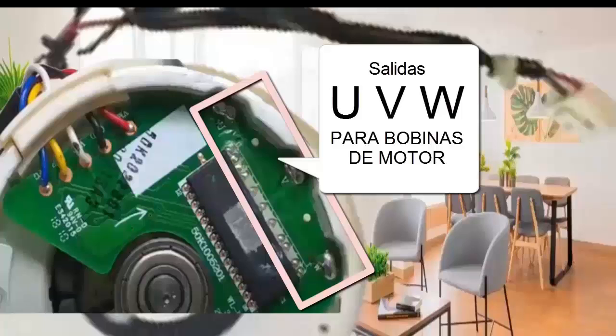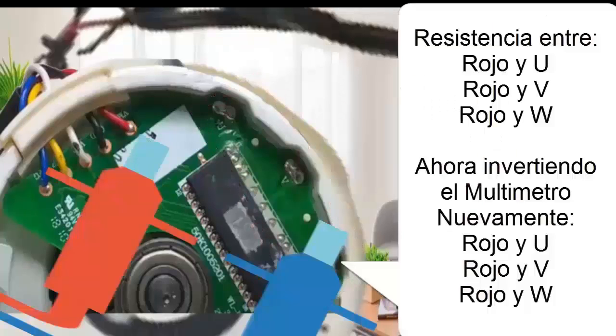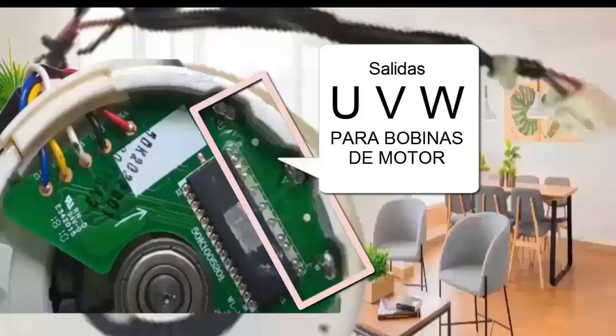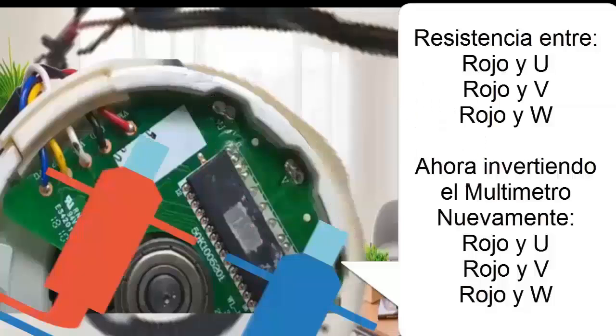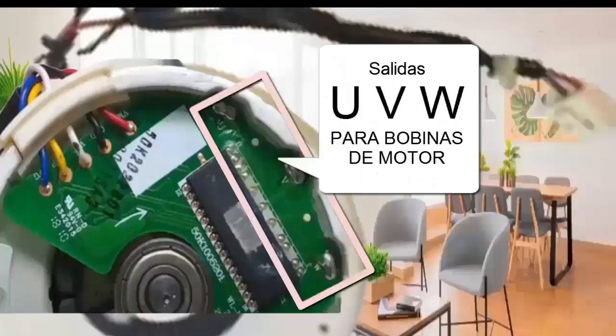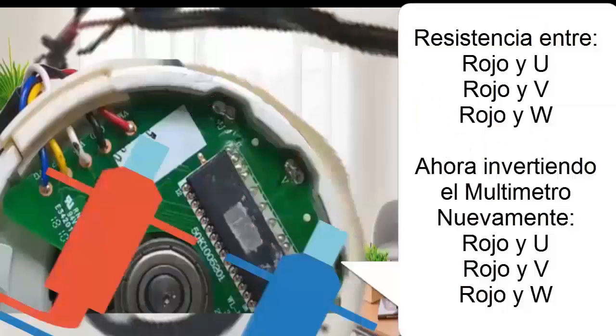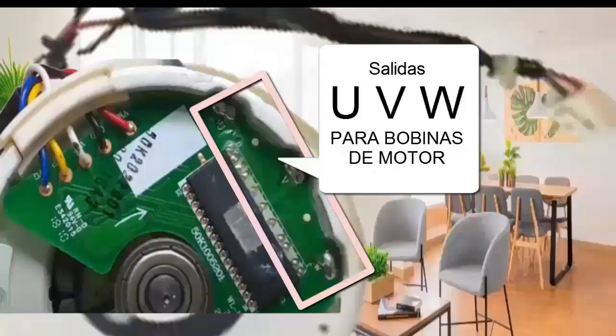6. Checking for problems in the electronic board. Measure electrical resistance with the multimeter from the high voltage power supply, red wire, to each of the outputs to the motor coils. All measurements should be the same. This procedure should be done with the red multimeter probe on the red wire of the fan and the black probe on each output of the internal BLDC fan board, then the same procedure with the multimeter probes reversed. If any measurement shows different values, the control board may have problems.